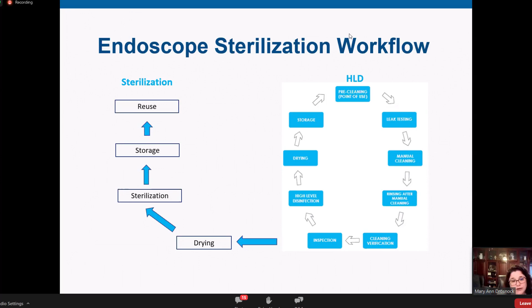You're really subjecting that scope to a lot of chemicals and will get damage potentially much earlier than you would by just doing one system or the other. Okay, so we know sterilization has a higher margin of safety built into it, but it is difficult, especially with certain types of scopes, to achieve sterilization. Example is your GI endoscopes, your regular gastroscopes and colonoscopes. There's not a lot of methods available for sterilizing them.